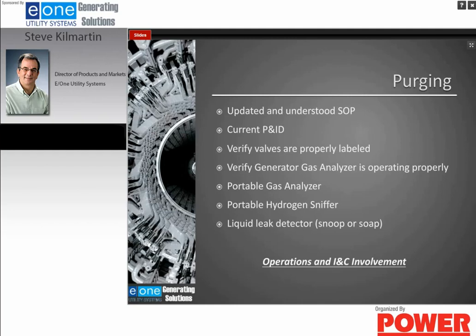On the bottom of this page, I have operations and I&C involvement. The reason for this is that I think it's very important that you have two people purge a generator. And this is from experience, I've witnessed purging of a generator where the operations group and the I&C group were involved. You can have one person reading the standard operating procedure and looking at the P&ID, and you can have another person that's actually exercising the valves and also reading the P&ID.